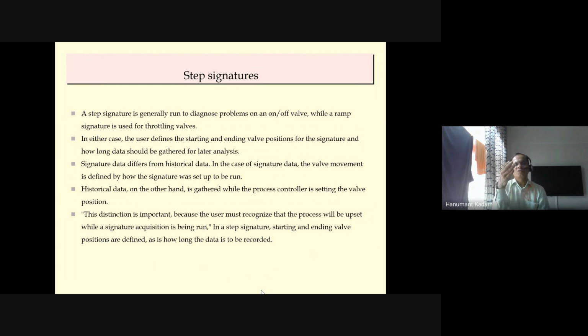With this, there are certain diagnostic features available here. You can see your step signature. This is one of the important parts. What does step signature mean? A step signature is generally run to diagnose problems on an on-off valve, while a ramp signal is used for throttling valves. Step means logic 0, logic 1, these two steps. In either case, the user defines the starting and ending valve position for the signature and how long data should be gathered for later analysis.